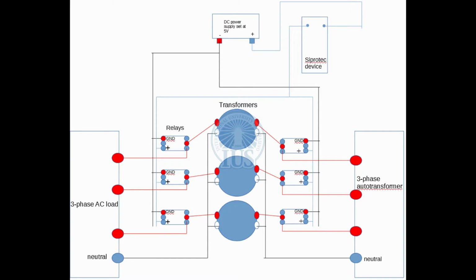As you can see, we again have a 5 volt DC supply because relays operate on 5 volts. We didn't need that in the image before because the Raspberry Pi can supply 5 volts itself, but now the relays are standalone, so we need a 5 volt DC supply. It is connected to the relays and to the Siprotec device. From the Siprotec device, there's an output again connected to all the relays. When the Siprotec needs to trip those relays, it closes its circuit, because in this case the Siprotec device is just like a giant smart switch. When it closes its circuit, a current can flow from the power supply to all those relays, and when the current starts flowing, the relays open.